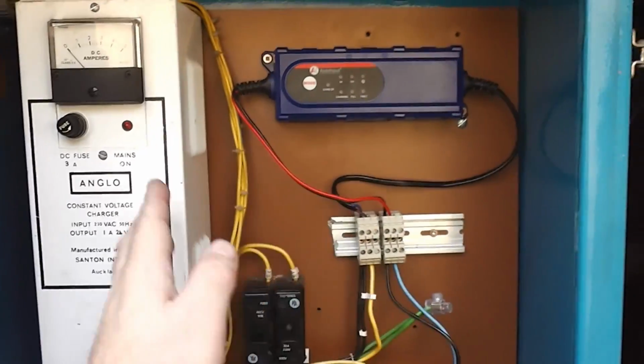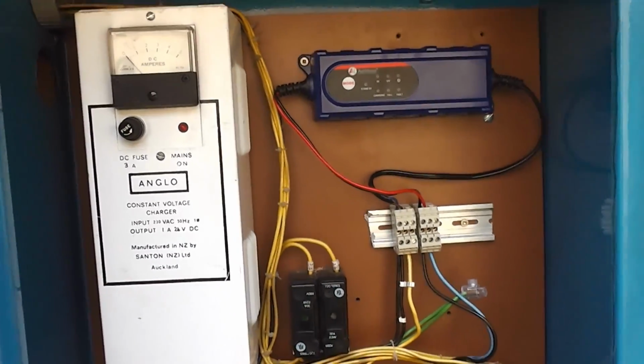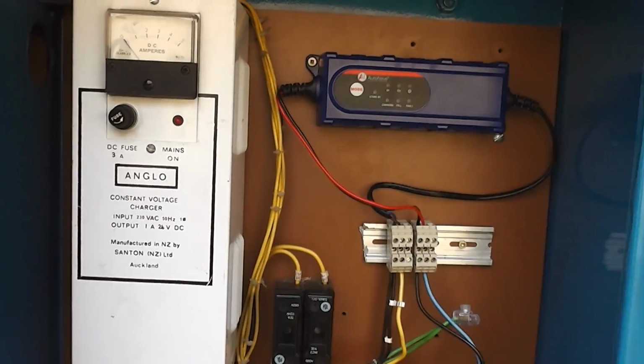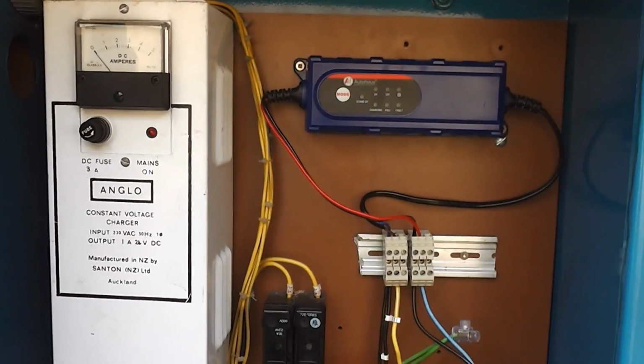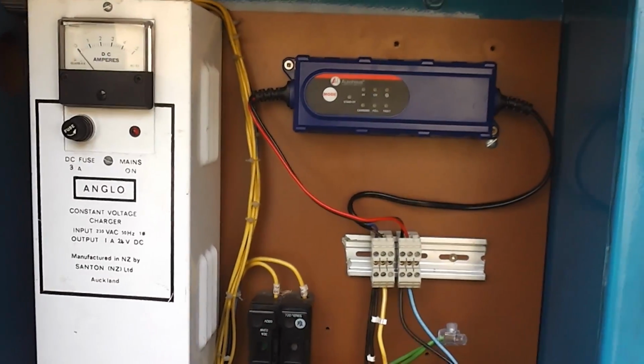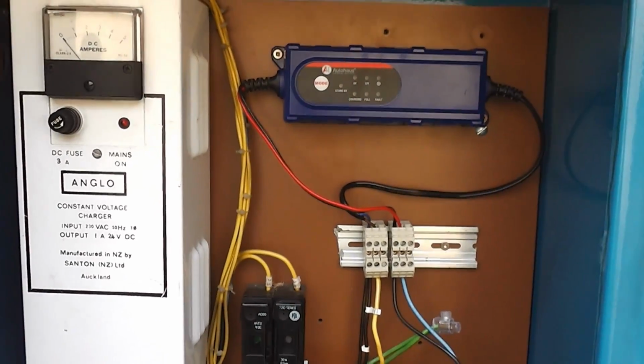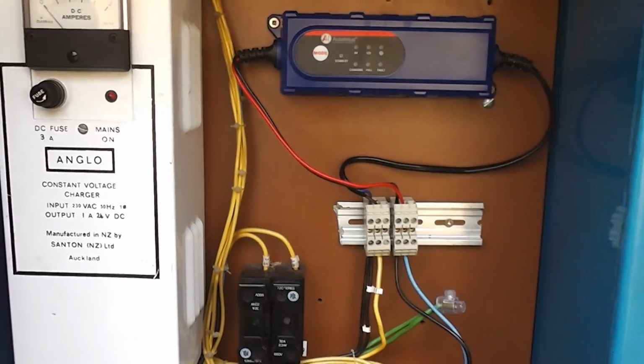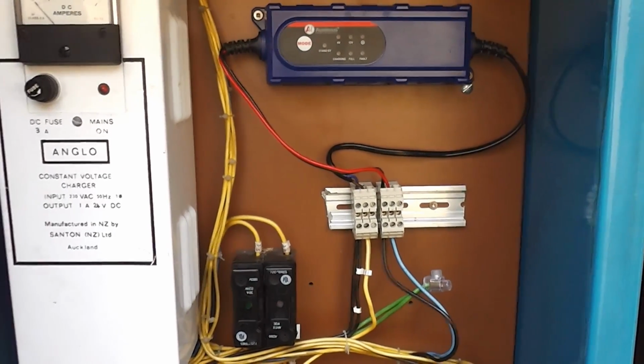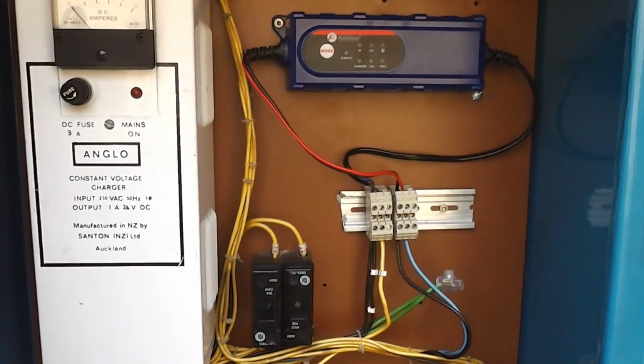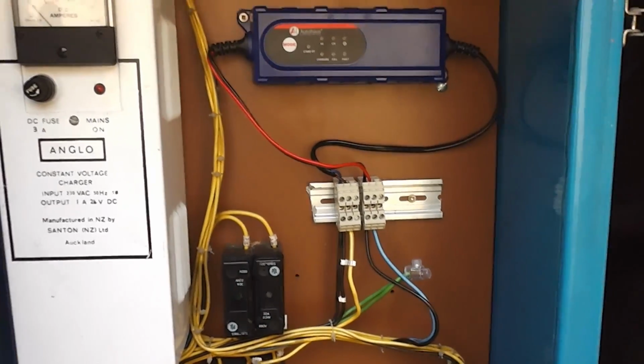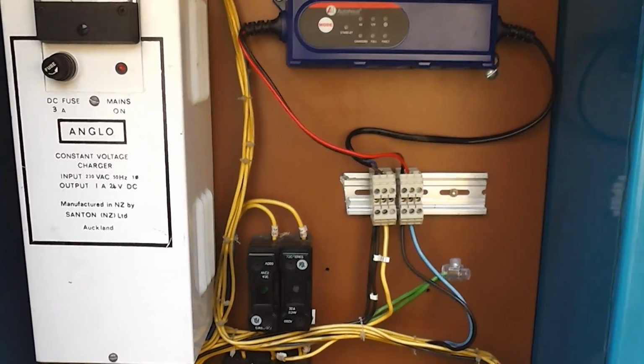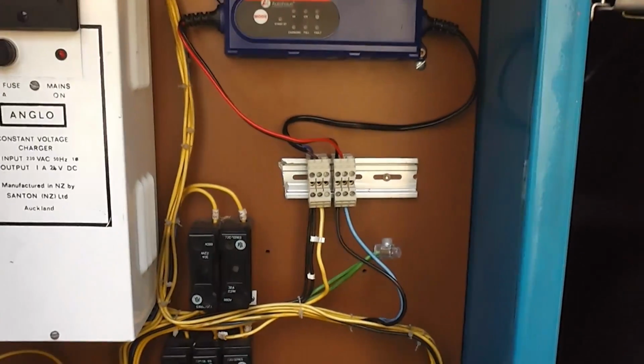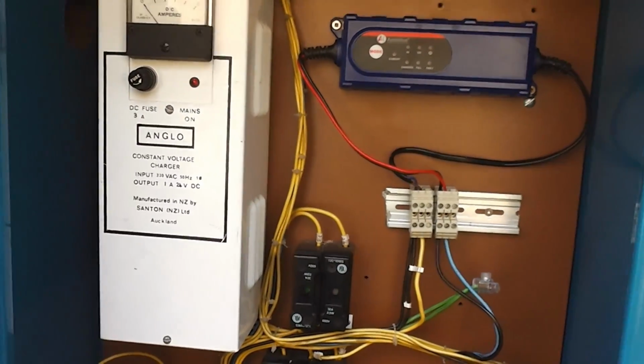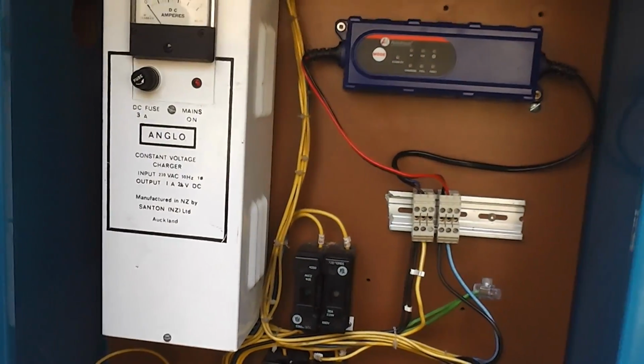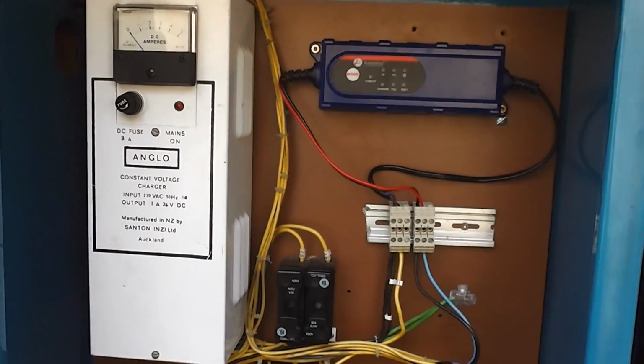The reason these are here is because standby generators like this will spend months and months sitting around doing nothing until one day the power goes off, and then they have to run. Normally a motor like this would charge up its own battery every day it runs, but because this sits here for months doing nothing, you need trickle chargers running constantly to keep the batteries topped up for when they actually need to be used.